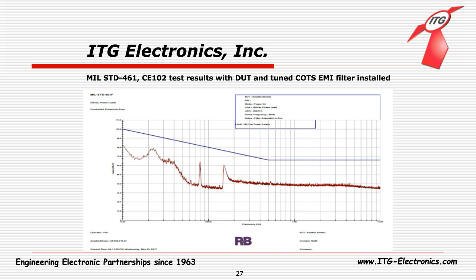Well, that's a good point. So I strongly recommend your ambient is at least characterized. Just for that reason, some of the labs, they don't like me, because I always make them do the test. And in some cases, we found peaks at certain areas that we could not get rid of. That's why we went back and asked them to do it, and they did the test, and we found out that the power coming in is the issue, not the unit.